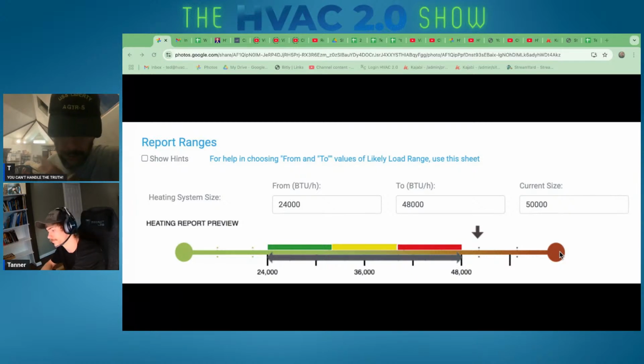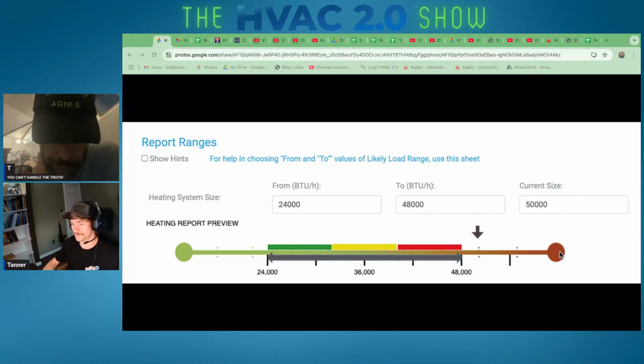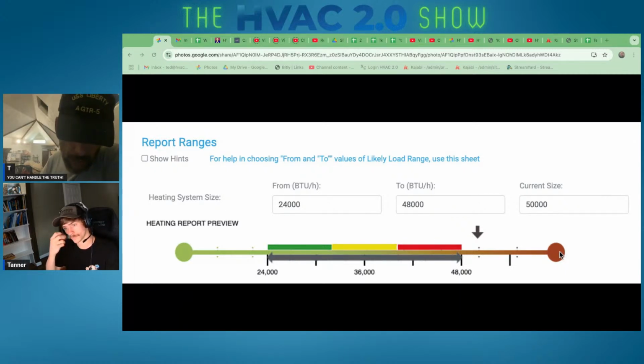Yeah. So if it says that the ductwork is good for 32,000 BTU, they probably don't want to go with 36, particularly if it's single stage, and probably not if it's two stage. You could go with 36 with a variable speed or modulating piece of equipment. I'm going to have to get five-stage out of my nomenclature now, aren't I?